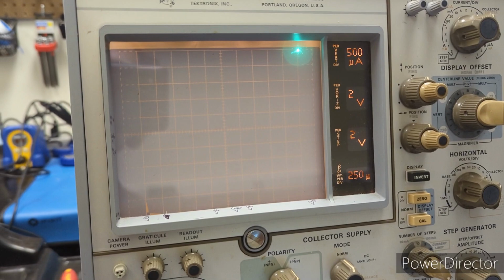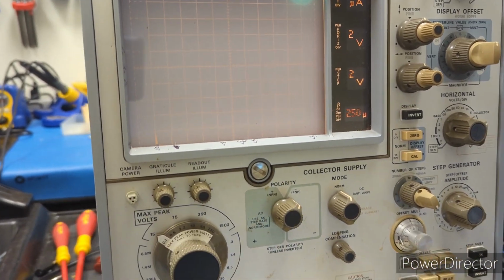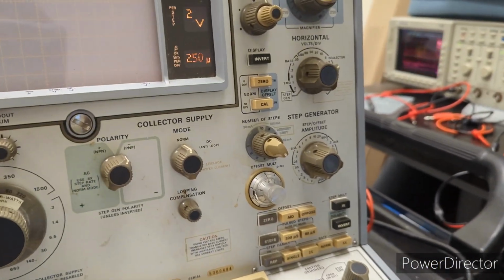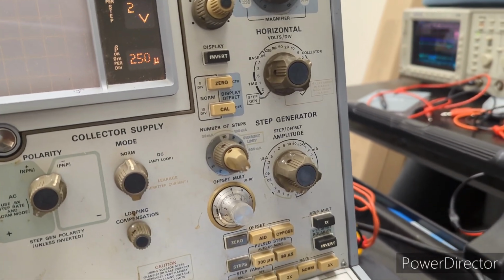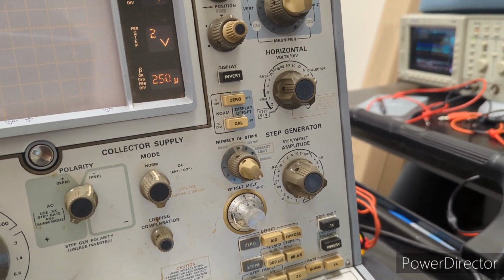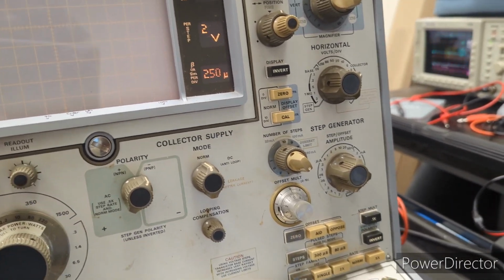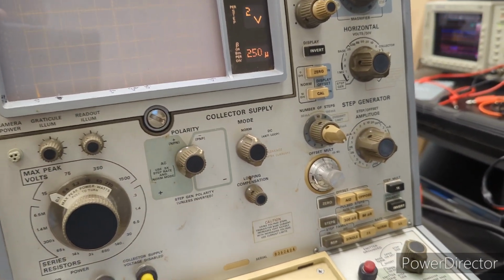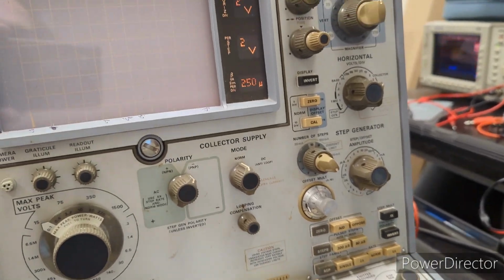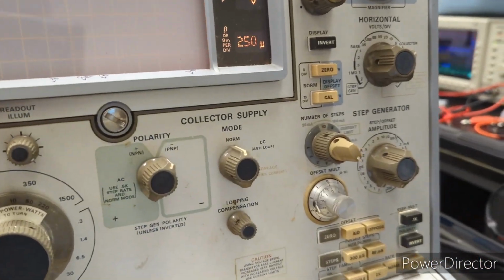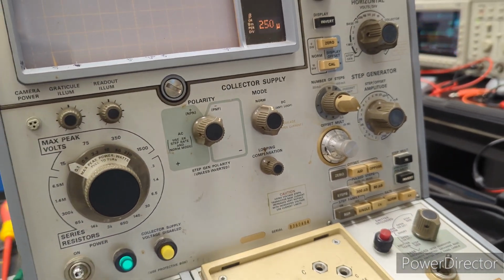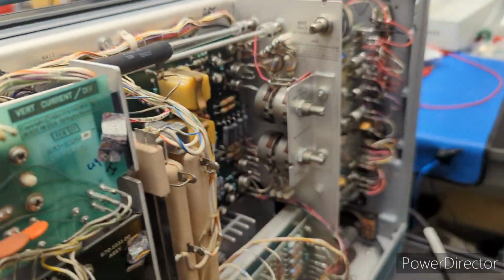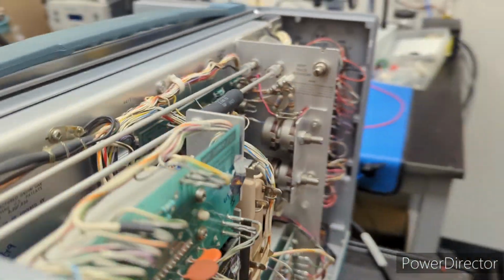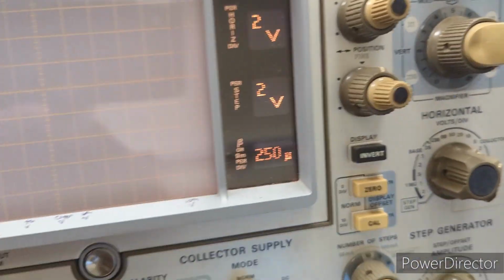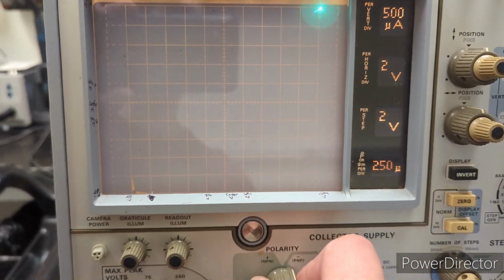All right, so I went back into the calibration procedure, and I went back to step 8, which is adjusting the display amplifiers, adjusting the balance of the horizontal and the vertical display amplifier.